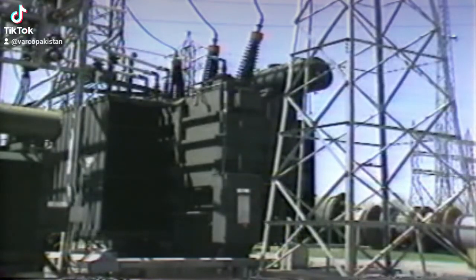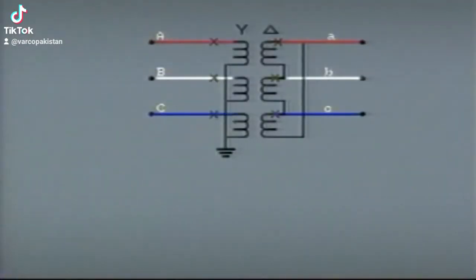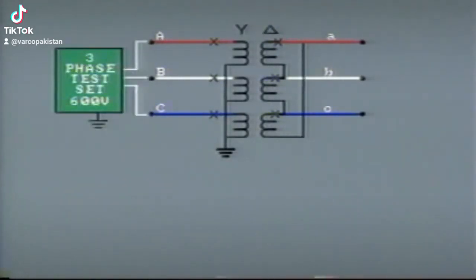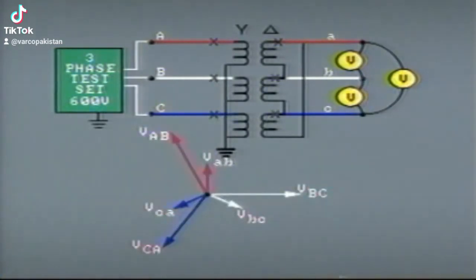For example, a three-phase transformer has internal connections. Also remember, there will be a phase shift between primary and secondary for a Y-delta connection. In most cases, phasing of the transformer would have been tested during installation by applying a low voltage, say 600 volts, to the high voltage side and measuring voltages on the secondary. Plotting the resultant phasor diagram will prove the voltage ratio, phasing, the phase shift, and phase rotation.